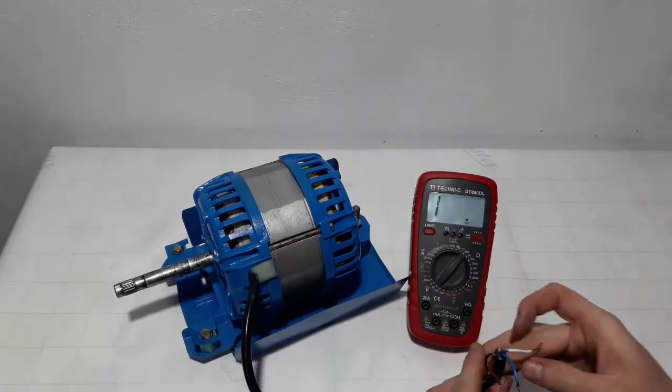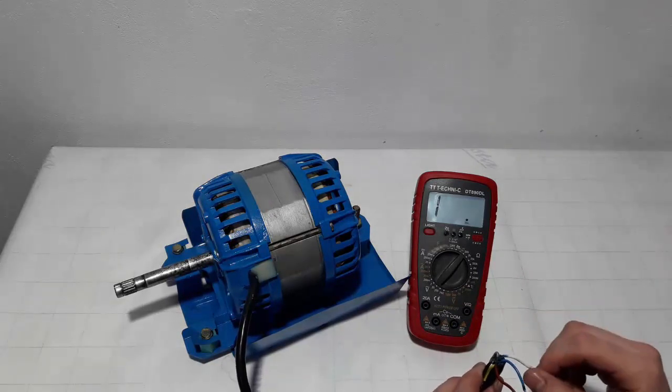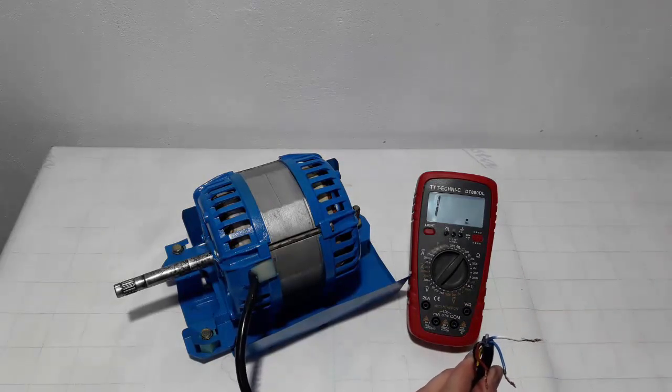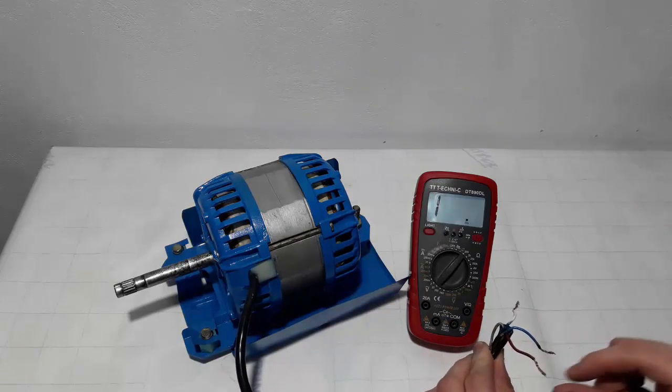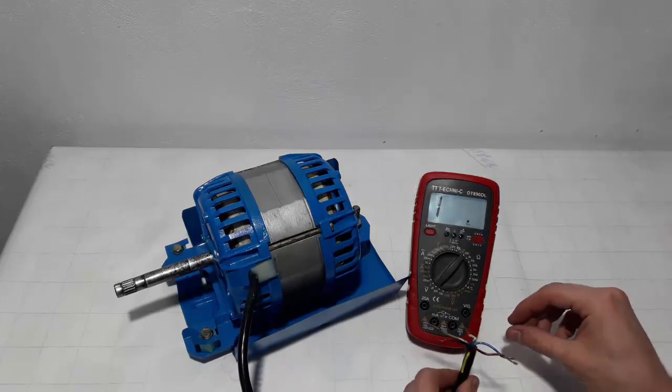To check: the resistance between the common and the low speed wires must be equal. However, the resistance between the common and the high speed wires shouldn't be equal.